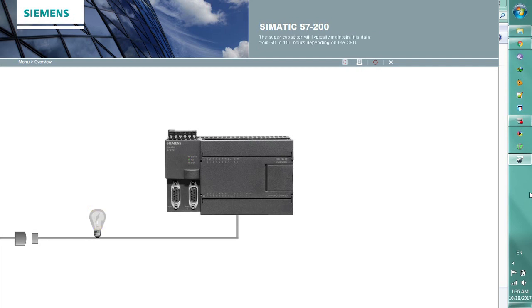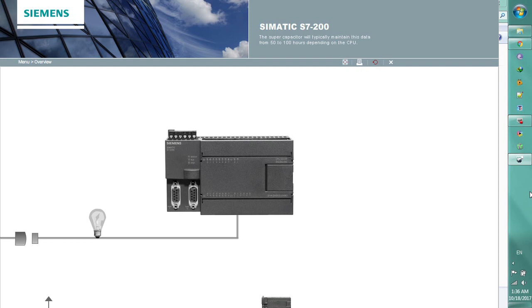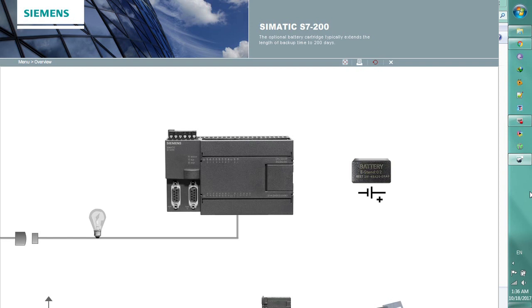The supercapacitor will typically maintain this data from 50 to 100 hours depending on the CPU. The optional battery cartridge typically extends the length of backup time to 200 days.